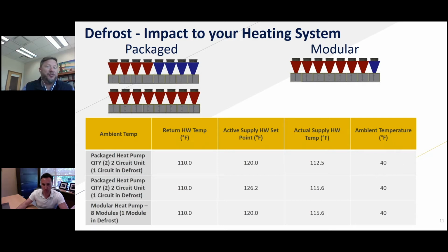Yeah, and so that's exactly it, it's a good question. And this slide really demonstrates again what that's talking about. If I have to go into defrost, which as an air source heat pump is a fact of life, you're going to have to. From a system design perspective, there are things we can do to mitigate the impact on the space. So if you look at this, as I said, 115.6 is really a worst case. And depending on how you set that up, let's say with multiple smaller units, if I go into defrost one unit at a time, we have the ability to maintain a very tight tolerance on the temperature leaving the heat pump system, versus if I have fewer, larger units, I have a much bigger impact on my system. And so if we start to think about it that way, well, then there are a couple different ways.